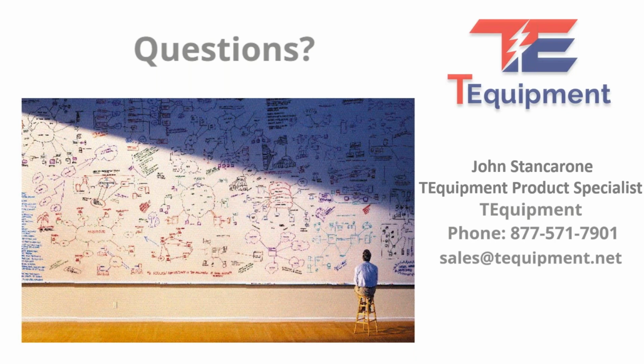Great, thank you. Third question we have is, can a low resistance meter be used to test the integrity of the ground grid and the grounding system? So grounding grid, grounding system, that is kind of a different application. There are instruments that are specific for that type of measurement, especially for the ground resistance, the resistance of the connection to ground. We have multiple instruments that can do that.